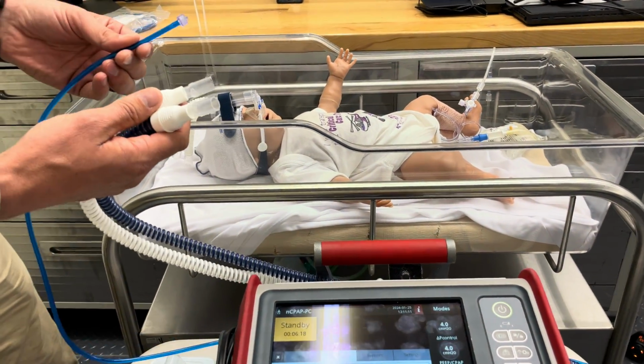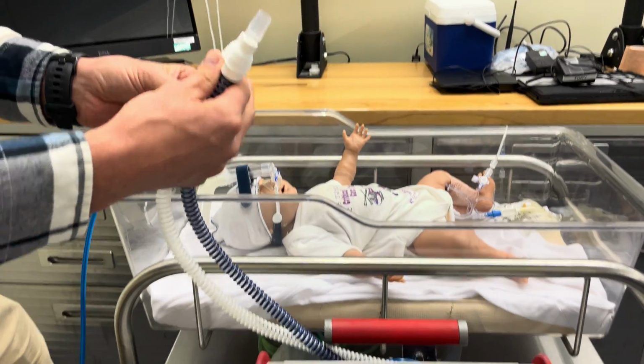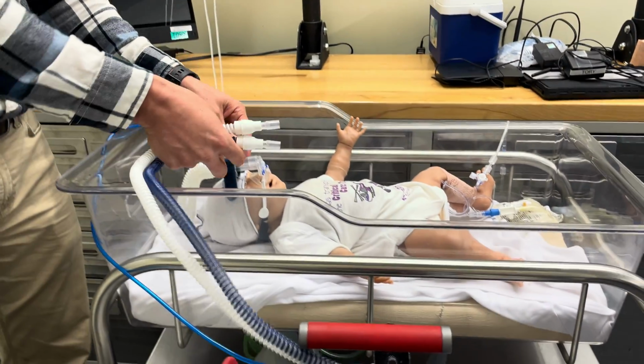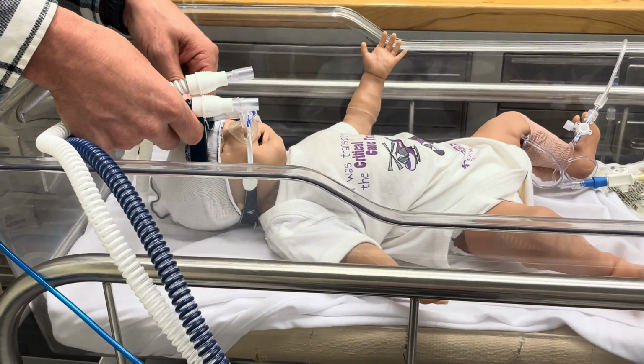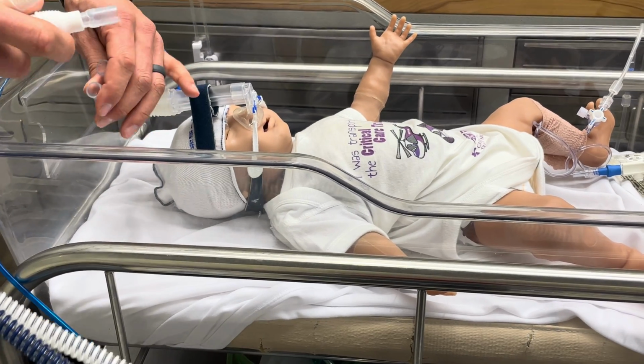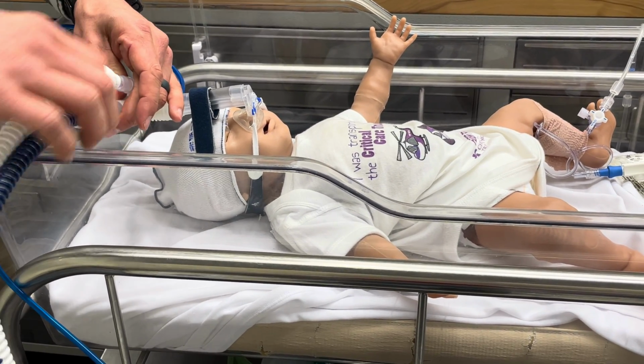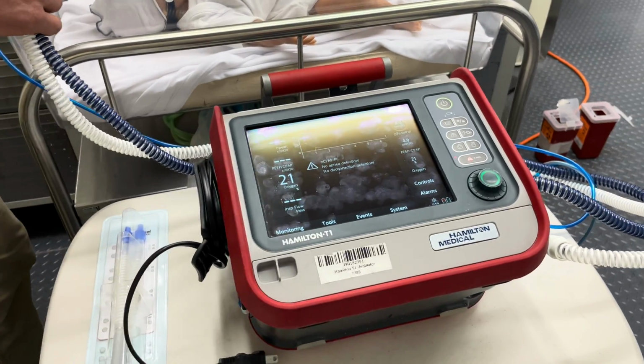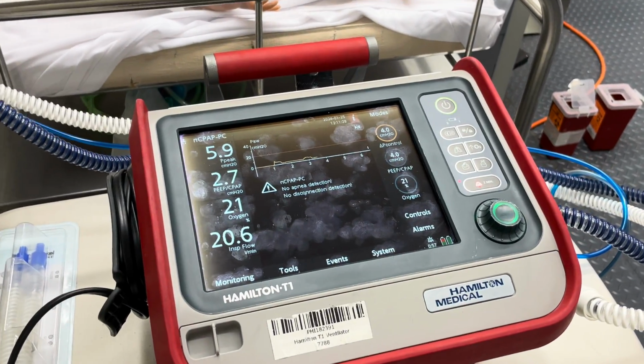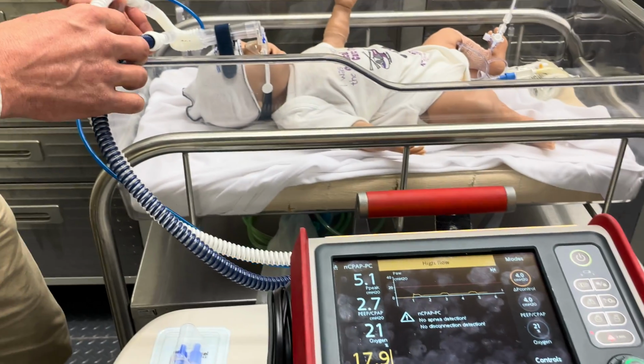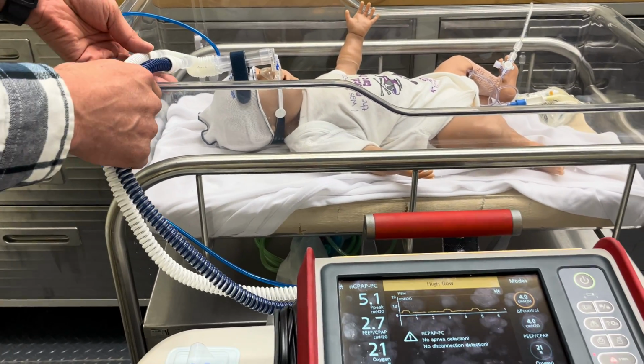What we're going to see is we have inspiratory, expiratory, and pressure sensor. The pressure sensor goes on the side of the trunk. We'll disconnect them from their ventilator. We'll connect them to our ventilator and hit start ventilation. It does not matter which one, the blue or the white, the inspiratory or the expiratory, goes to. It's going to work the same either way.